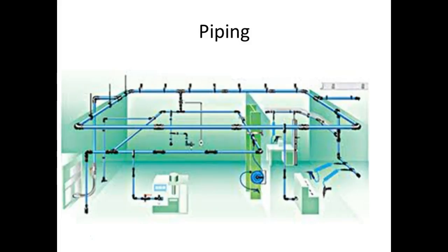So notice the closer we get to the device, the flow is going down. At the top pipe, we've got all the flow, so that top pipe up there is supporting the flow of everything in the system. And when we start branching out, the pipes can start getting smaller because the flow is divided out among the system. Well, no, it's to reduce the cost of the system.